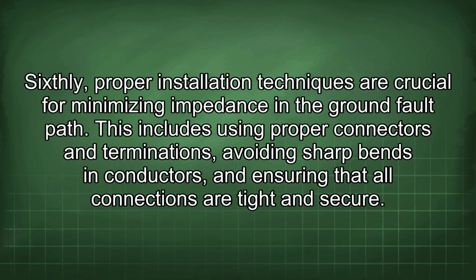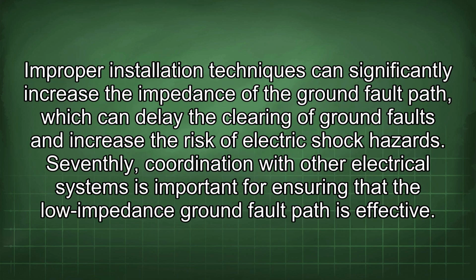This includes using proper connectors and terminations, avoiding sharp bends in conductors, and ensuring that all connections are tight and secure. Improper installation techniques can significantly increase the impedance of the ground fault path, which can delay the clearing of ground faults and increase the risk of electric shock hazards.